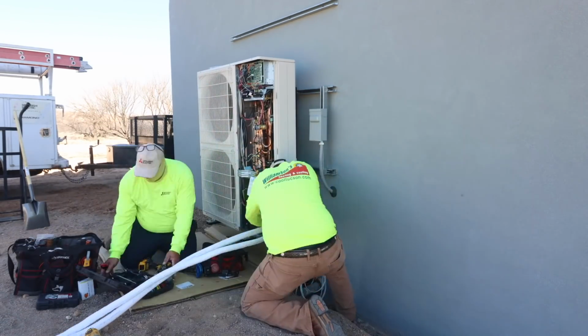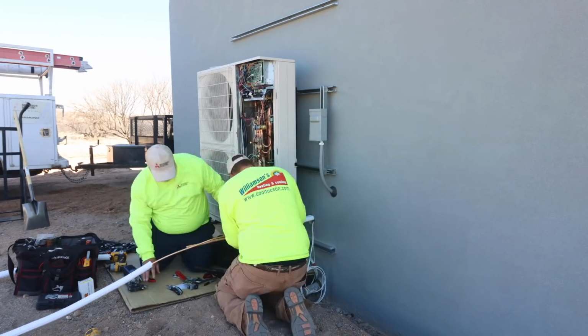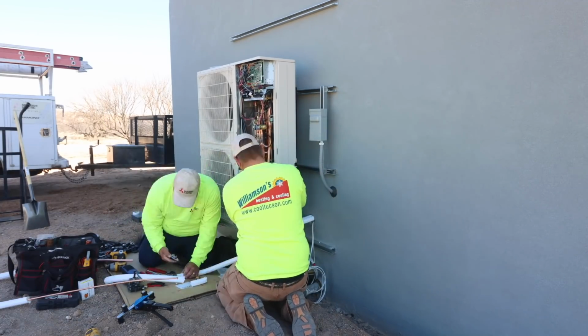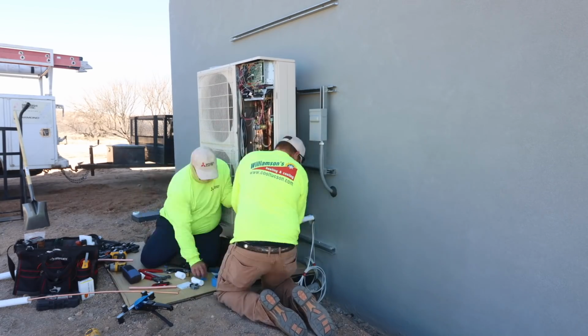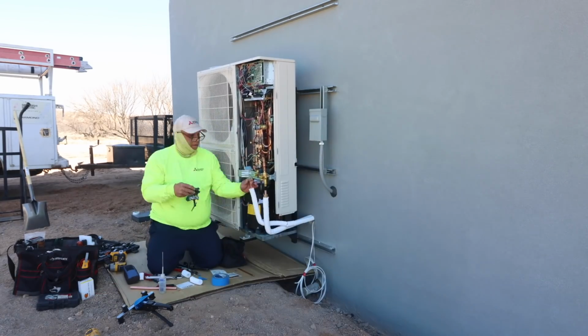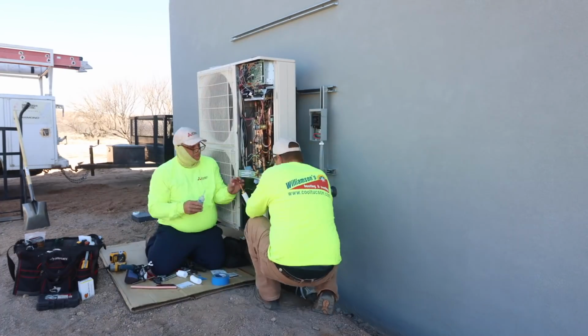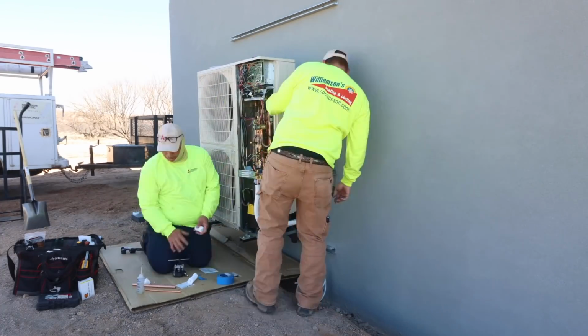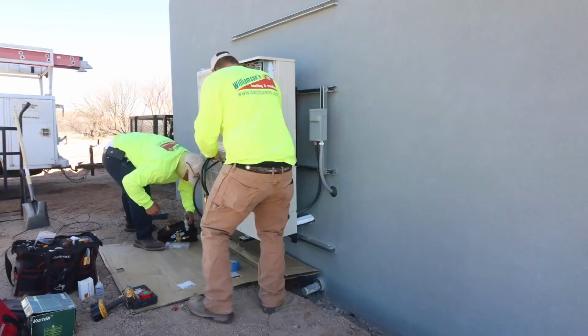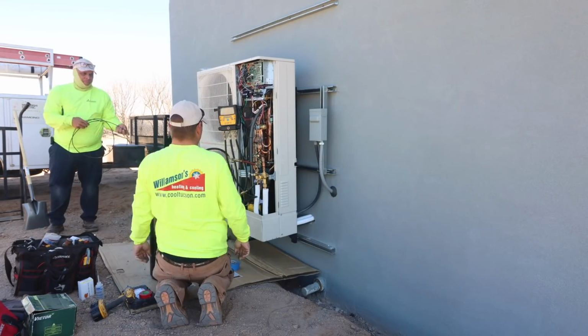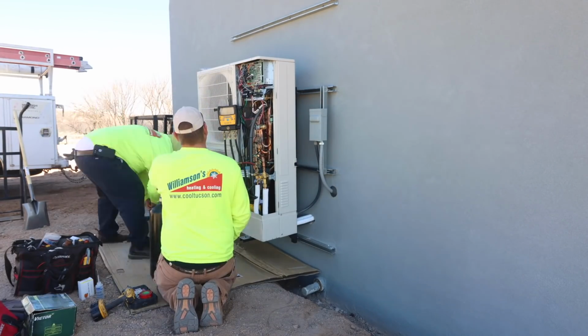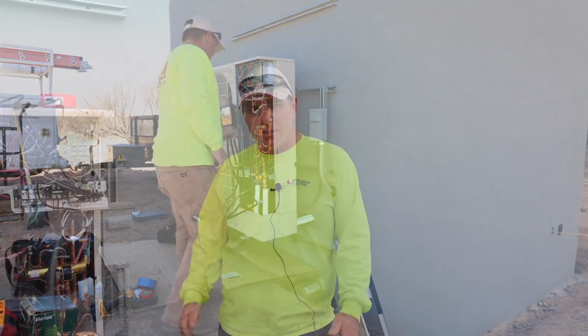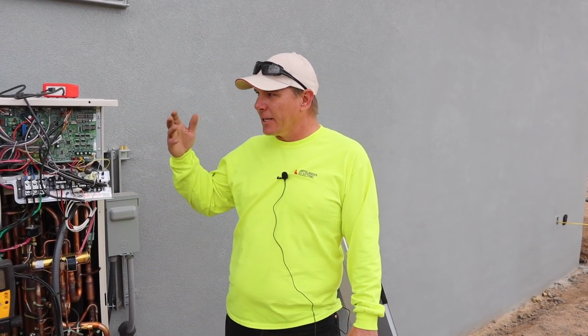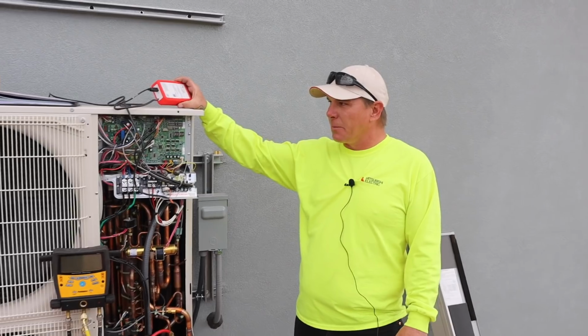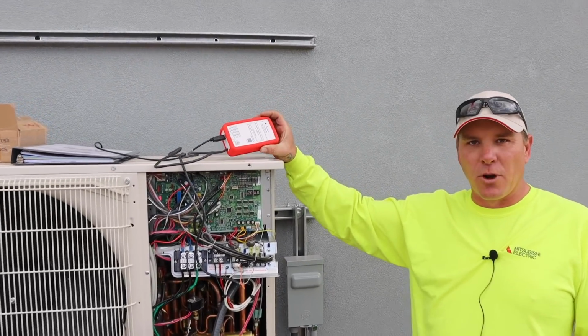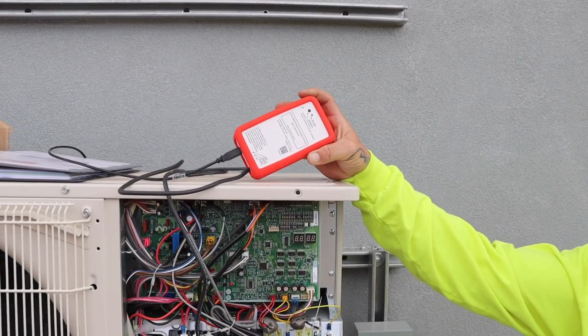So what we did then is we ended up doing a vac on the system. We actually did a triple evacuation. We got our microns down to 290, and we were able to do a rise test. Everything seemed to pass with that. We added our additional refrigerant, which is 8 pounds, and now we've finally started the system up. So what we're doing now is checking amp draws and dialing the system in with the MNet tool, which is going to make this system run at its peak performance.